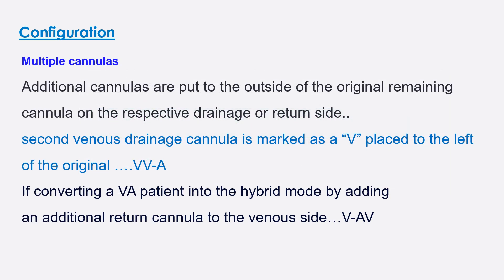The first part of configuration covers multiple cannulas. Additional cannulas are added to the outside of the original cannulas on the respective drainage or return side. For example, in VA ECMO, if we need to add a second venous cannula, it is marked as V and placed to the left, making it VV-A. If we want to convert a VA patient into hybrid mode, we can add another return cannula to the venous side, resulting in V-AV ECMO.